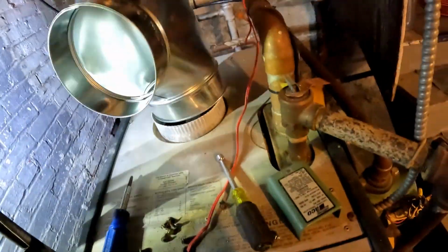Okay, so what we're going to do now, I removed the draft hood and vacuumed inside. This T is going to go here. I just have to crimp the outlet. The barometric T is going to go right on top of this, and then the barometric will go inside. So this is the inducer, what they had. It's a Field Controls unit. This is upside down, but I think you can see. So that was pulling everything in through the room and making an inappropriate draft.